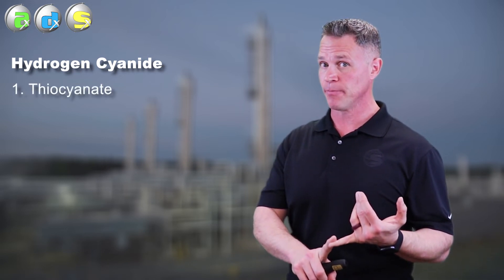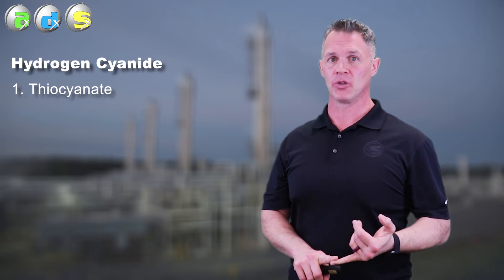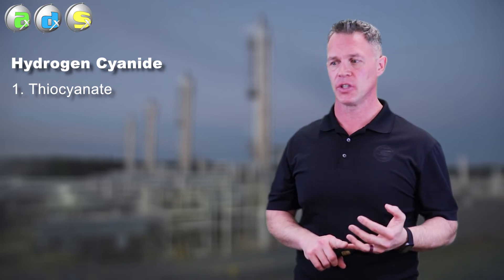Next, we have something that's pretty much associated only with refineries, hydrogen cyanide. Hydrogen cyanide is a nasty reactive acid that comes into the amine plant. We see it form thiocyanate. It's pretty much the only thing that forms thiocyanate, so look for that in your analysis.